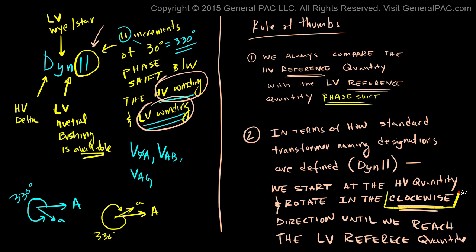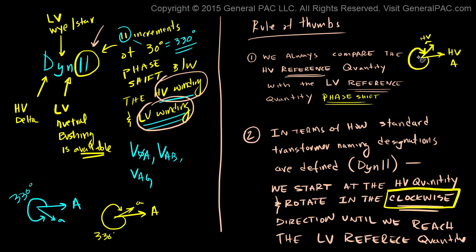This is a key point: we rotate in the clockwise direction until we reach the low voltage reference quantity. So once we have this high voltage reference quantity for winding A, we rotate clockwise until we get to the low voltage reference quantity for winding A on the secondary side. This is 330 degrees, as in our example — so in this type of designation, we're rotating in the clockwise direction.